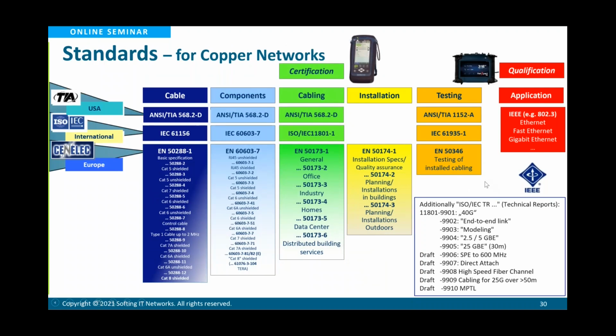The testing is then done according to the American TIA standard 1152-A in the Americas. In international standards, it is IEC 61935-1, and in Europe it is EN 50346. That is the testing of installed cabling, which describes the performance the testers have to have.